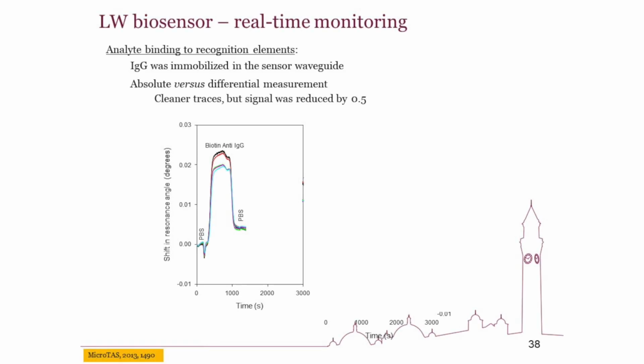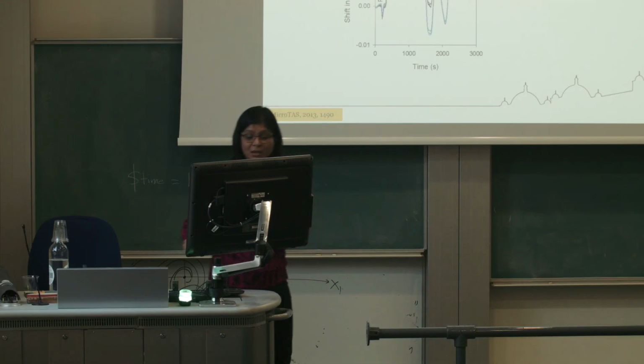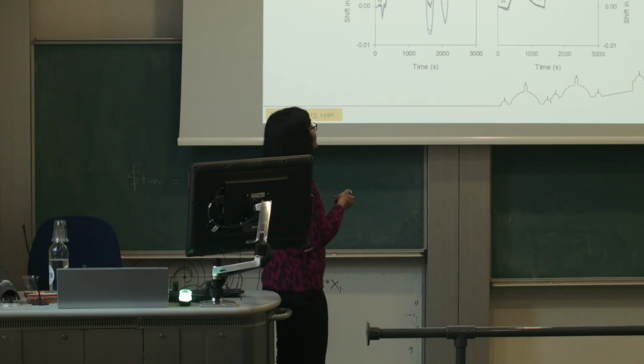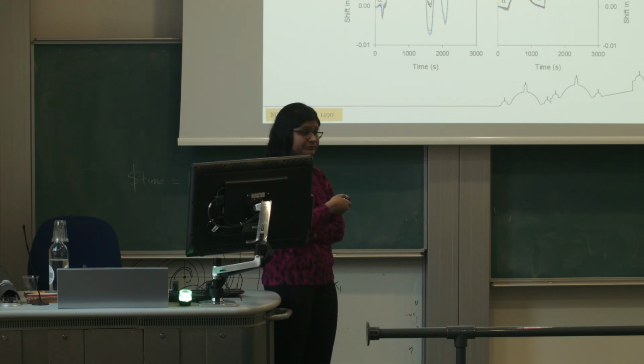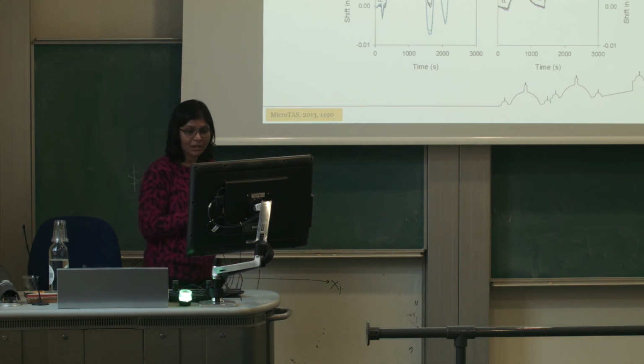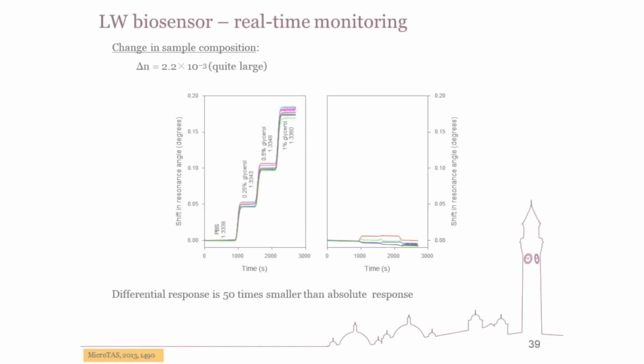So to show that, we attached IgG in the sensor waveguide, and this bit is from the sensor and this is the reference. And here we just recirculated streptavidin. So these are absolute signals, and we can see that the absolute signals are just horrible because of the recirculation. But if we look at the differential signal, they are so much cleaner. Okay. So in the differential signal, the signal is reduced by half, but at the same time, the signal to noise ratio is improved.